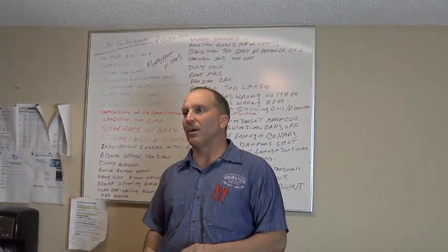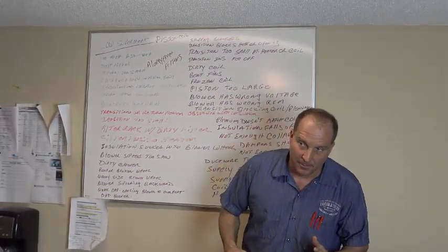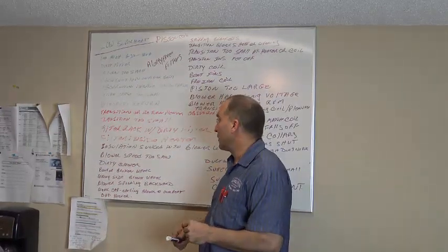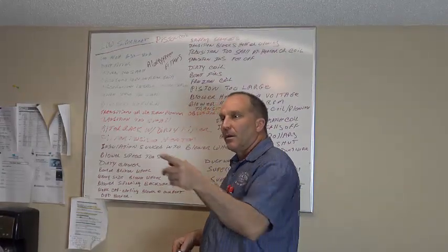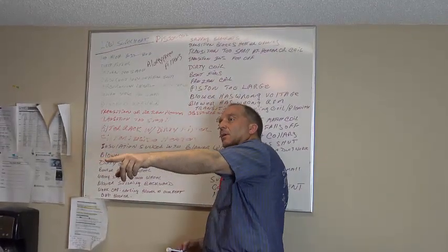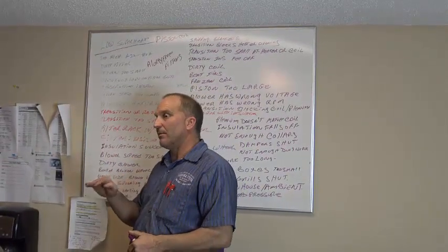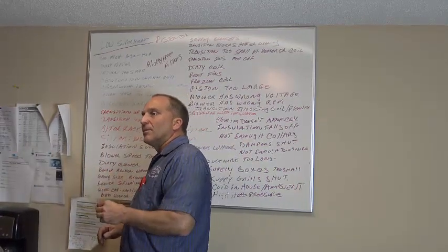5-ton system, 2,000. 3.5-ton system is how much, Adam? 3.5 ton, 4 times 3, 12, 14. 1,400 CFMs, you got it, okay? How about a 2-ton system, Mike? 800. 800. 2.5-ton. 1,000. Okay? 400 CFMs per ton. Okay? Based on a 0.5 static pressure.